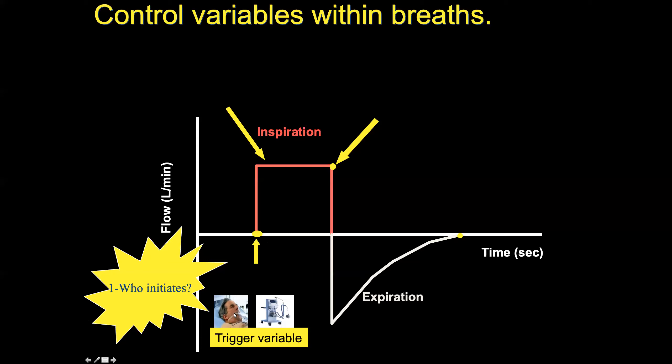With the patient, there are two ways initiation can occur — we call this the trigger variable. It is by a pressure trigger or a flow trigger. To summarize: initiation or starting of a breath can be controlled by only two players — the ventilator, which initiates by elapse of time, or the patient, who communicates by dropping pressure or drawing some flow. That is called a flow trigger or pressure trigger.